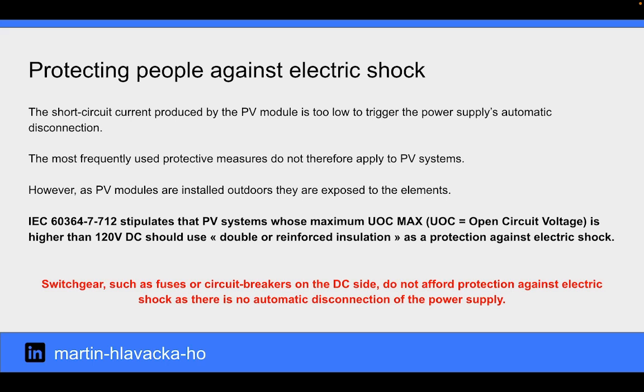IEC 60364-7-712 stipulates that PV systems whose maximum open circuit voltage is higher than 120 VDC should use double or reinforced insulation as a protection against electric shock.